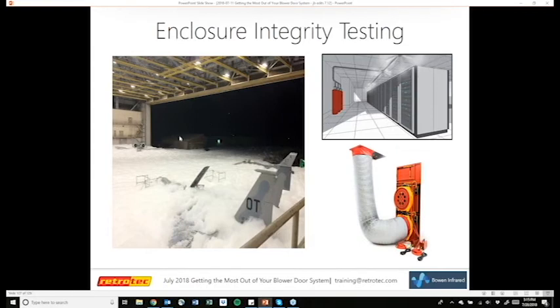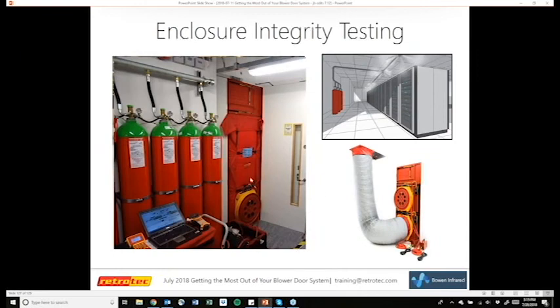And so this is a picture. I'm sure you guys are wondering what's going on here. This is an Air Force base that's housing some fighter jets, and it did not get tested for its fire system before they loaded everything in there. And so the first time they fired up a jet and rolled it out, it set the fire alarm off, which then dropped this fire suppressant foam down, which then ruined a bunch of jet engines and caused a lot of money worth of damage. So what happened was they called one of our customers out, and they did some blower door testing to see how to properly ventilate everything to make sure that's not going to happen again. So what you're seeing here, this stuff that looks like clouds, that's actually foam. And then this fire suppressant is stored in tanks, which then goes through piping to serve the room.